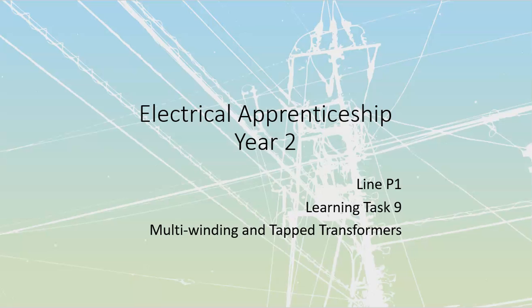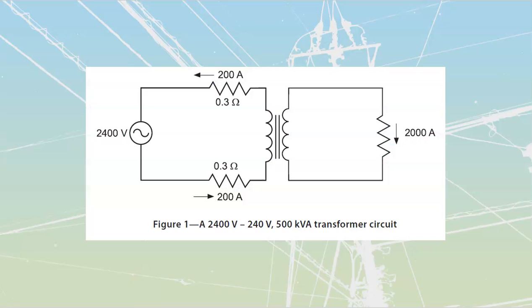A multi-tap transformer is a really common thing, and usually it's been placed there for compensation. Here we are showing a circuit that has got some line drop off of it. Line drop is where the resistance of the lines itself causes a voltage drop over top of those lines.